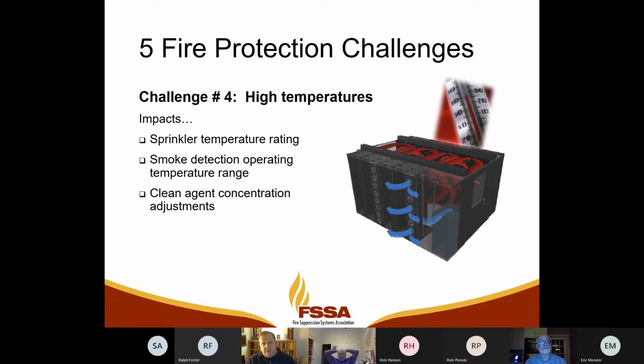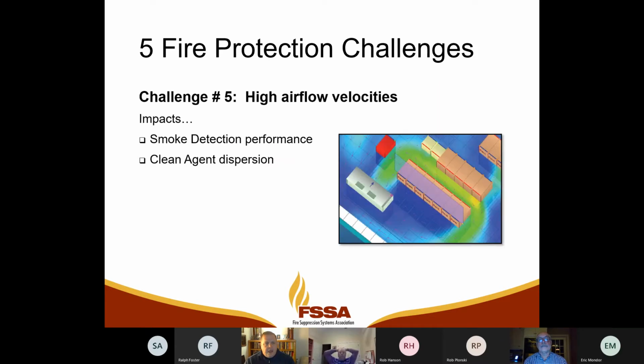High temperatures, challenge 4. Because of the increased rack density, more power, more heat given off, the hot side of the servers, the hot aisles, have gotten hotter in these situations. It can impact the sprinkler temperature rating that may be there, the smoke detector operating range, and it may affect the clean agent concentrations because those are affected by the operating temperature.